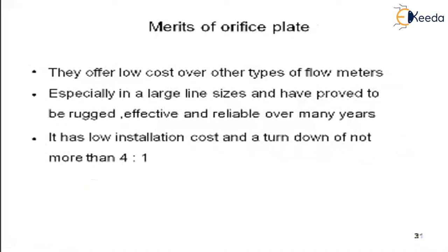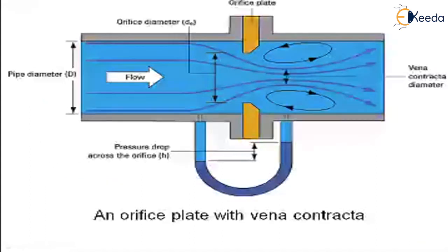Orifice plates are low cost, available in different sizes, robust in construction, effective and reliable, and can be used for longer periods of time. They have a low installation cost and a turn-down ratio of four to one, meaning the rangeability is four to one.